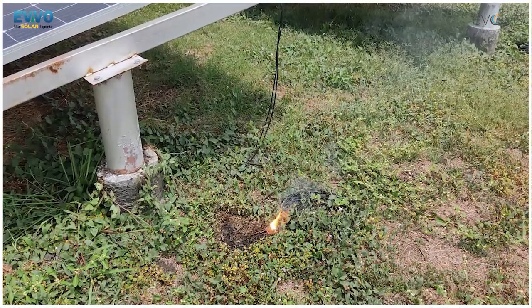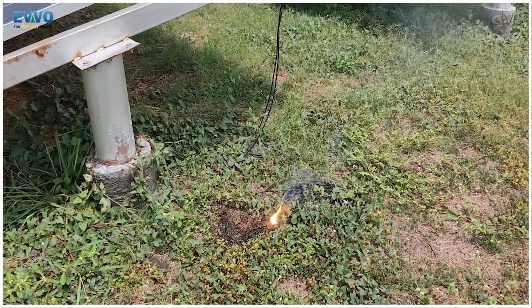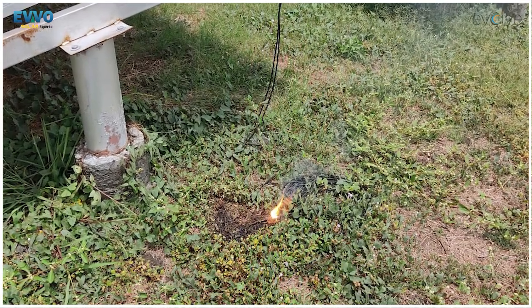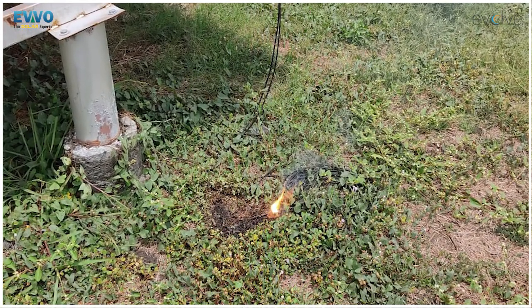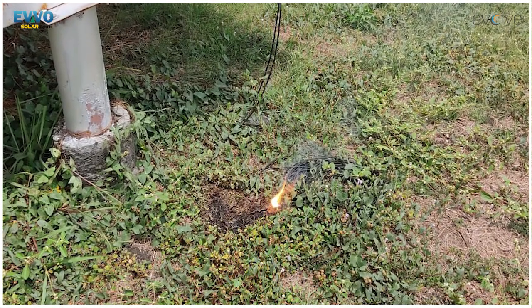Now, this pit should not be anywhere close to the pit where you have grounded your solar inverter, that is your AC side, because these pits, when they don't work - for example, if they get dried out or don't have good conductivity - then this lightning, which is trying to get dissipated into the earth, can actually take back the route and go back into your inverter, damaging it. No problem with your solar panels though. Your DC side, the solar panels, the solar structure, can be grounded to the same pit as the lightning arrester - you don't have any problem with that. But with your solar inverter, never ground it to the same pit as your lightning arrester, because it can also get back into your inverter.